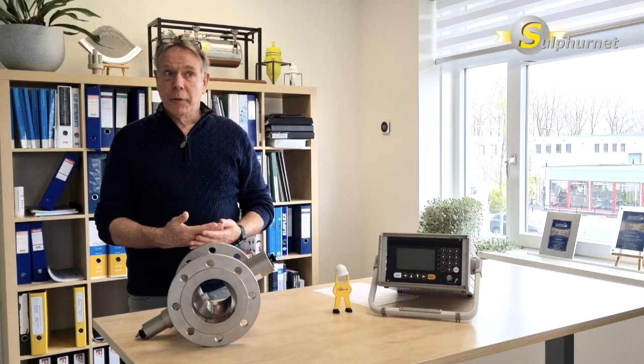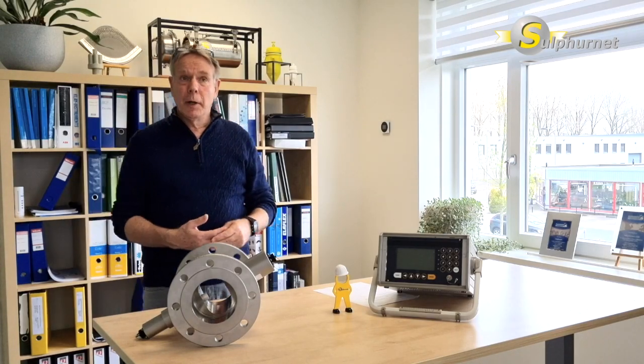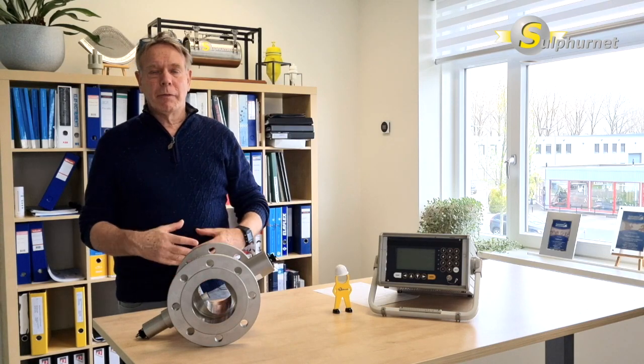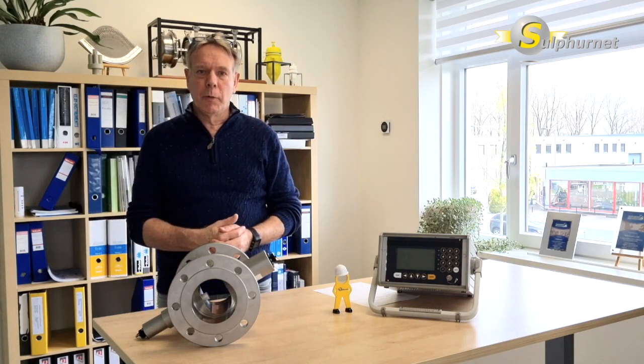There is a polishing filter installed after the pressure leaf filter that will reduce ashes as well, so you can continue, but you are fouling your polishing filter at that moment. So you have to make a decision on what you're going to do when the ash level exceeds the preset value.